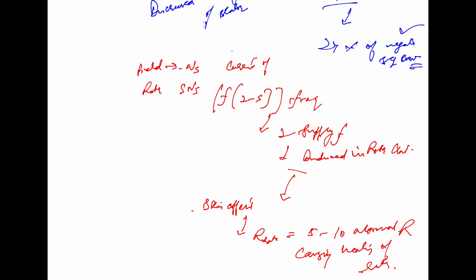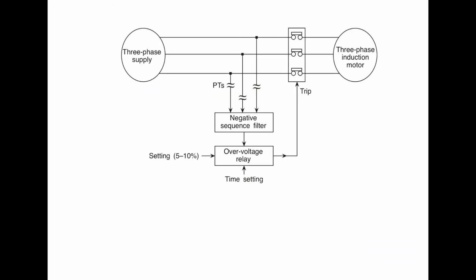So, for large motors, any unbalance in the supply needs to be detected as early as possible and corrective action needs to be taken. Now, figure A shows a scheme for detecting the unbalanced supply voltage. In this case you will see the negative sequence filter is there, then the over voltage relay is used to trip the circuit. So this scheme is used for that.